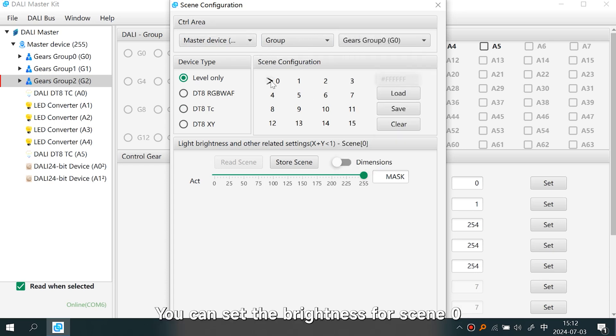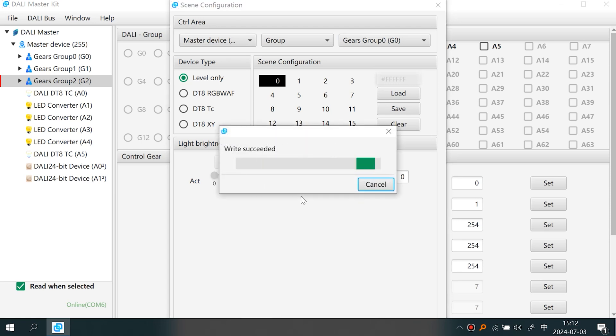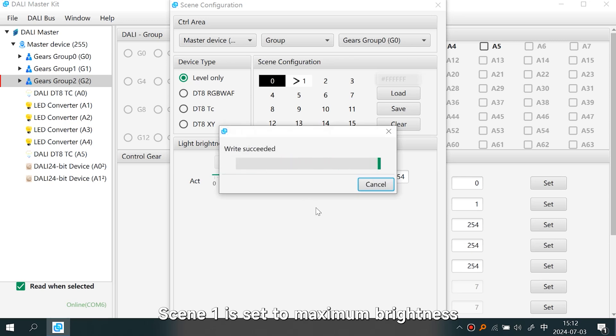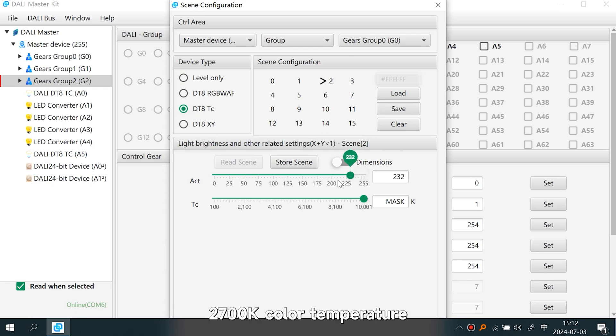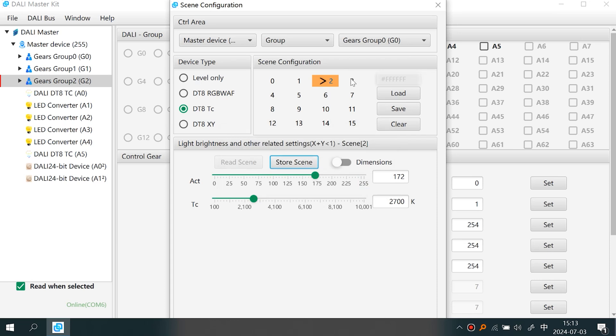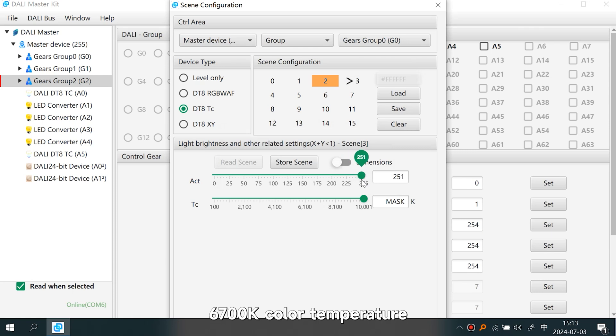You can set the brightness for each scene. Set Scene Zero brightness to zero to turn off the lights, then click Store Scene. Scene One is set to maximum brightness. Scene Two is set to a lower brightness with 2700K color temperature. Scene Three sets a higher brightness with 6700K color temperature.